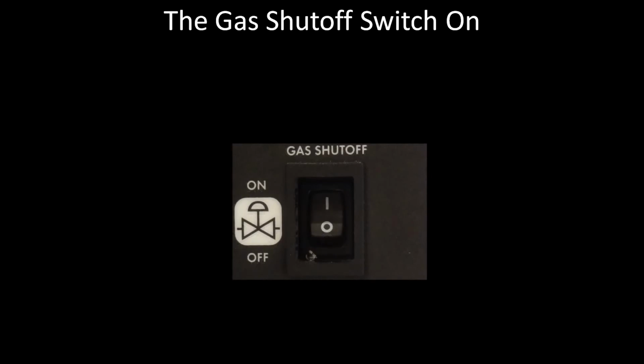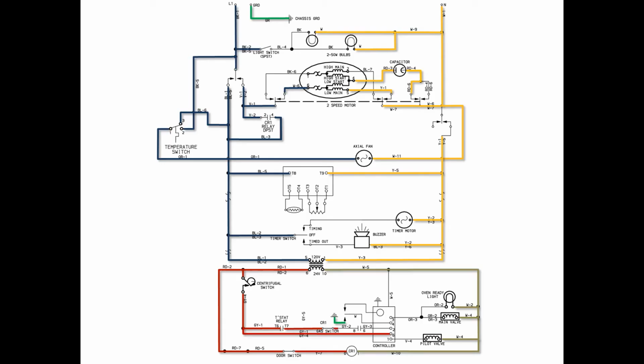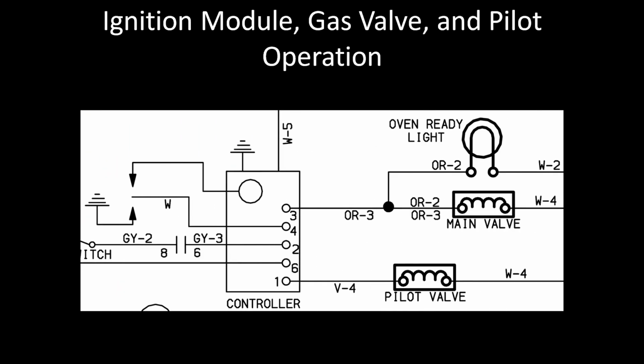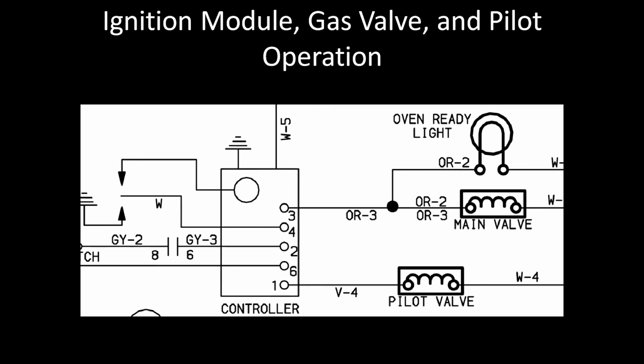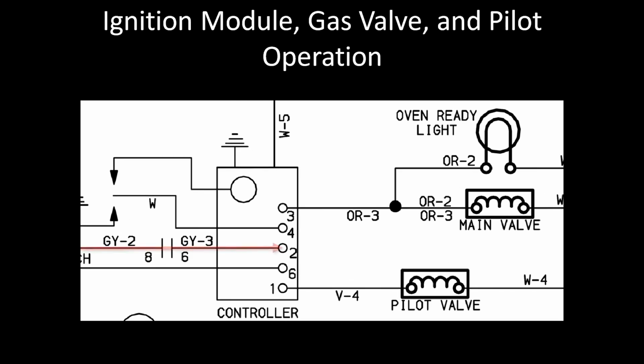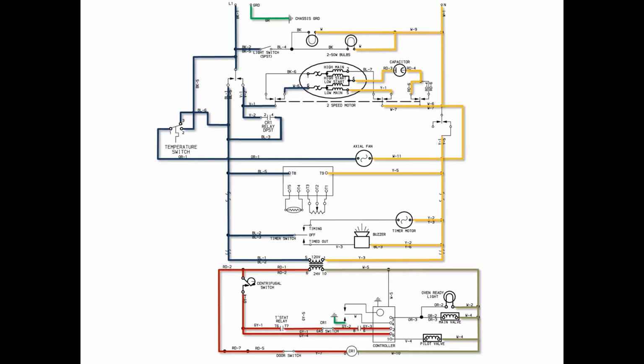Next, we will turn on or close the gas cutoff switch. This sends voltage to the ignition module. Once voltage is received at the module's terminal 2 THS, the focus shifts to the ignition module, the gas valve, and the pilot assembly. When 24 volts AC arrives at terminal 2, the module has a 4-second pre-purge. It then sends voltage to the pilot valve and spark to the pilot.